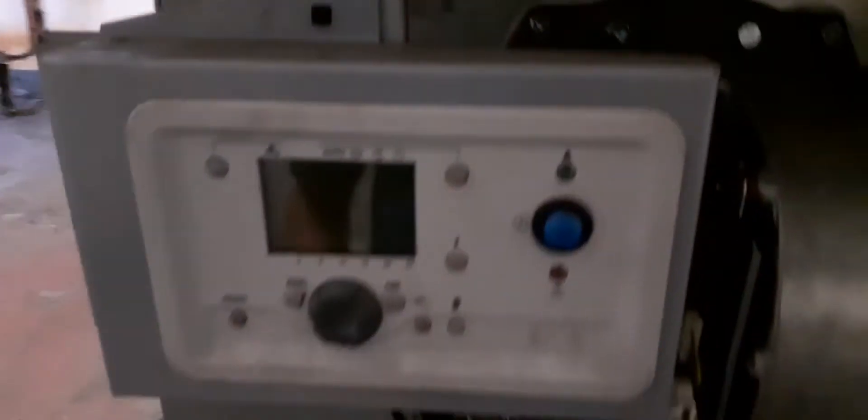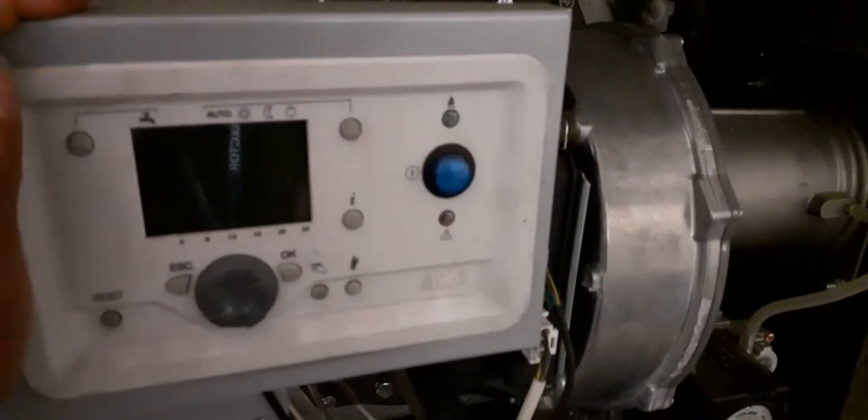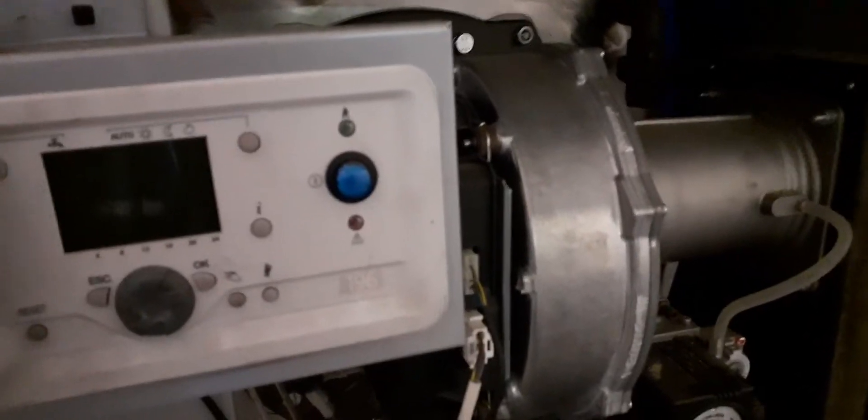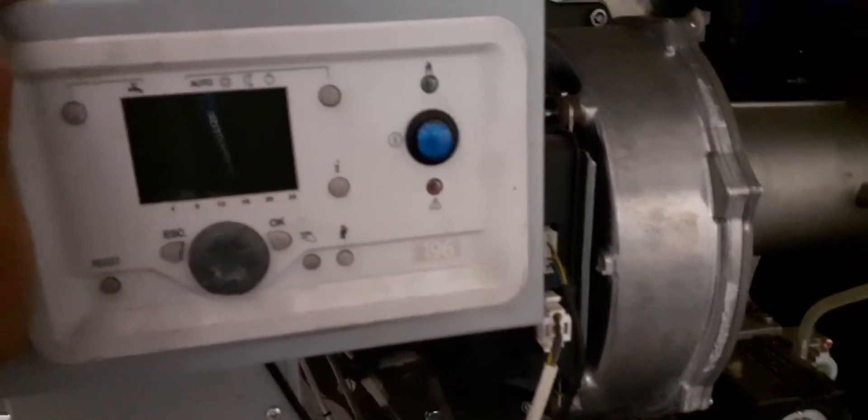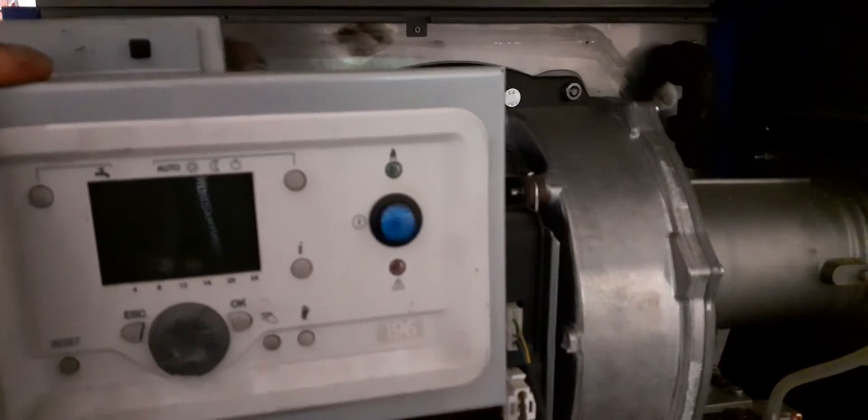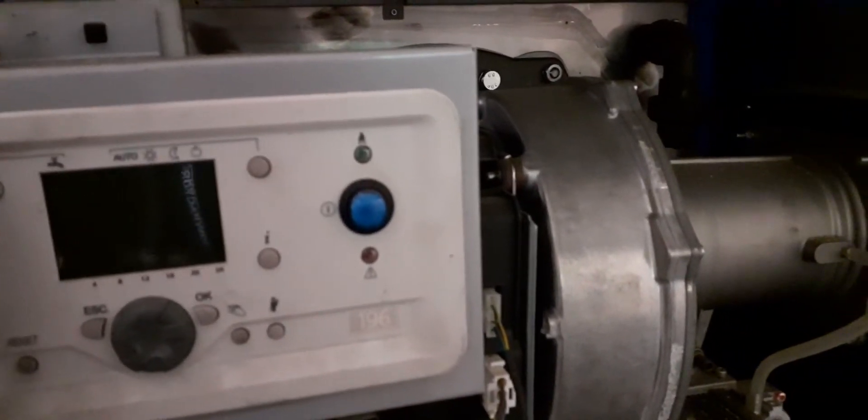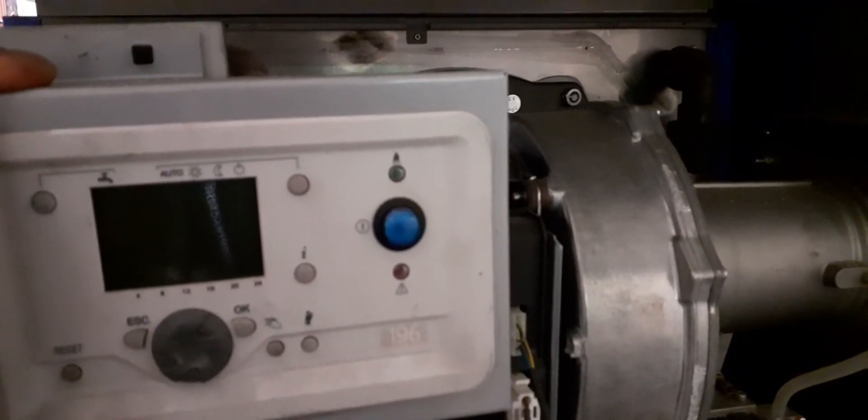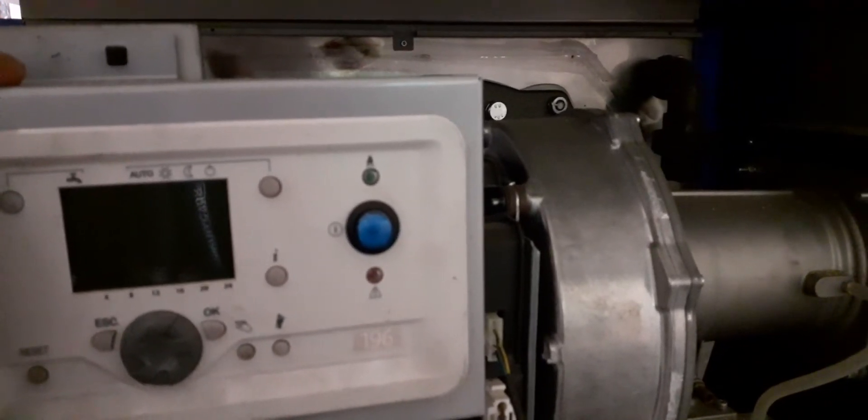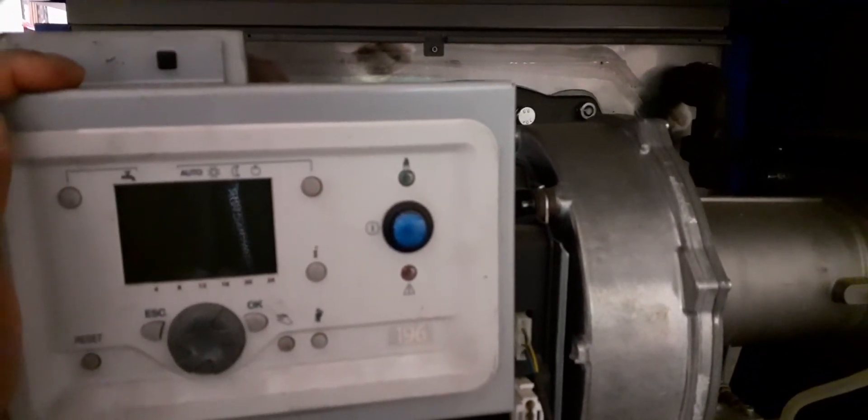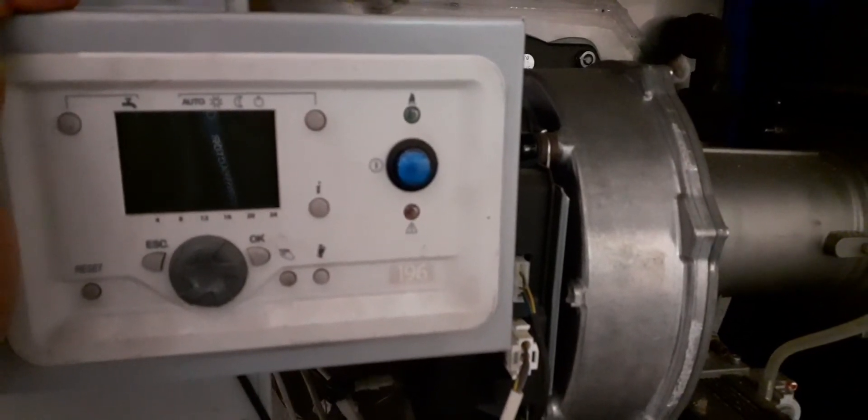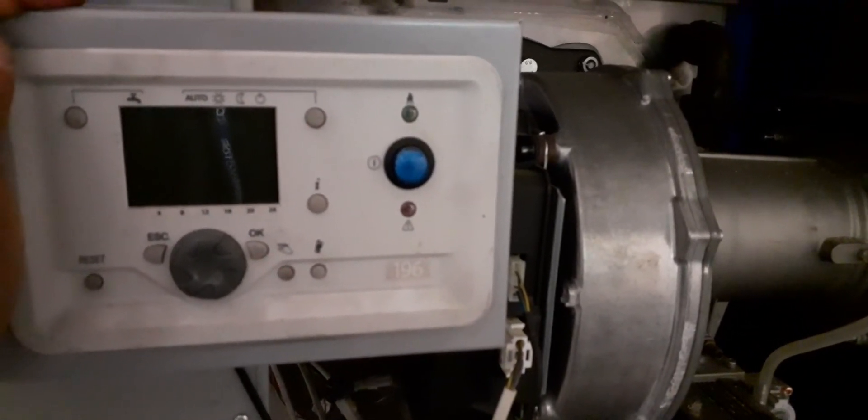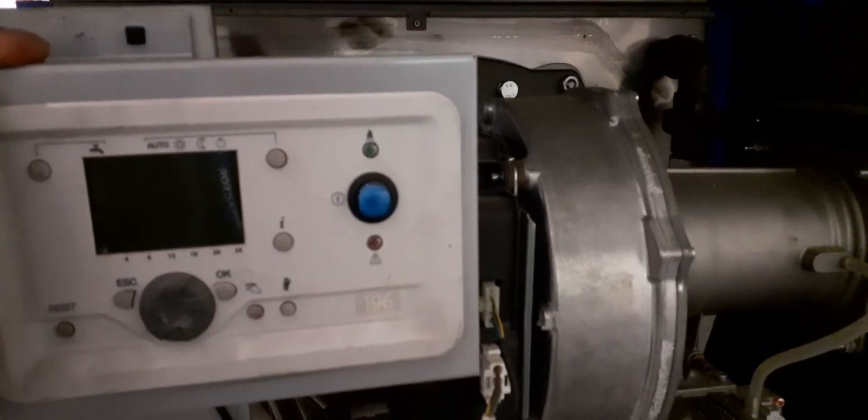Okay, word of advice: ensure that the pumps are running and that there's a demand for heat. As you can see, I've turned this boiler on and it looks as though the pump behind it isn't operating, or the sump pump or something to that effect isn't running on the boiler. So there's no circulation going through it. I need to go and investigate that because the boiler's kettling and overheating very quickly, as you could hear.